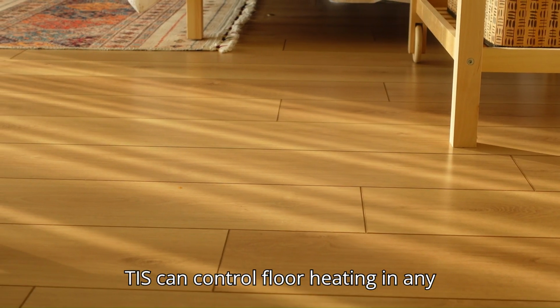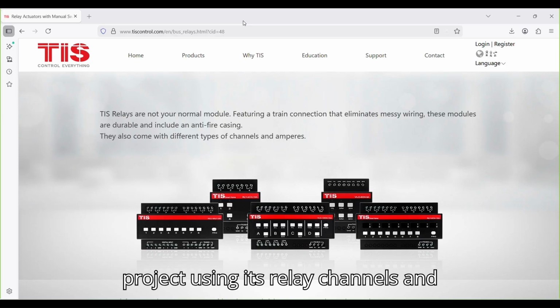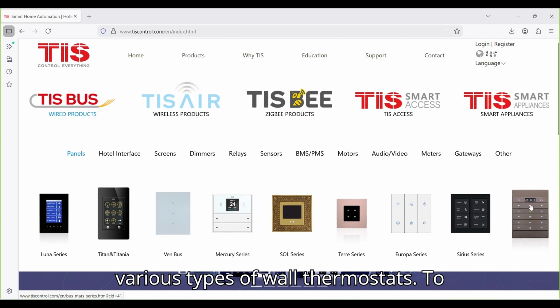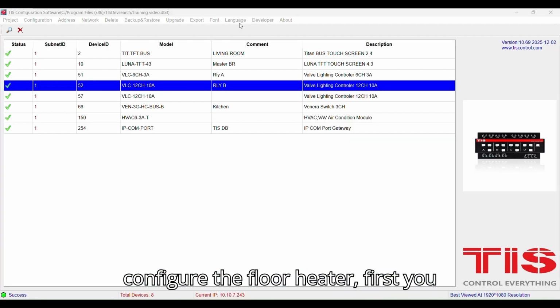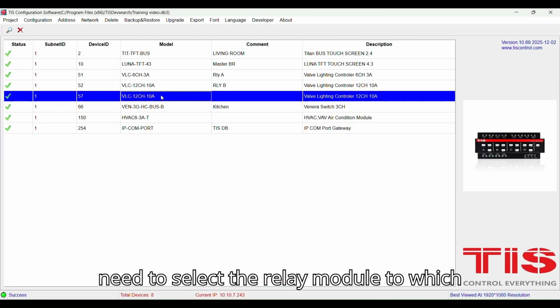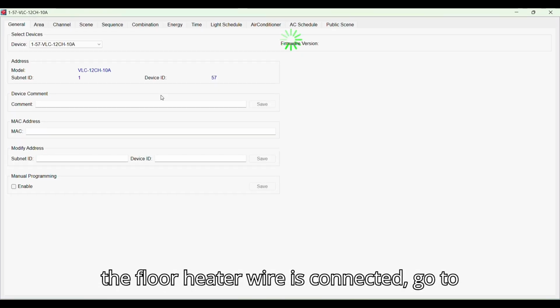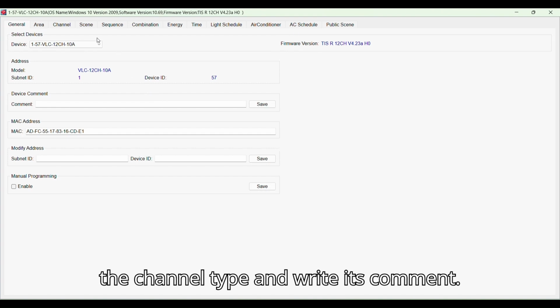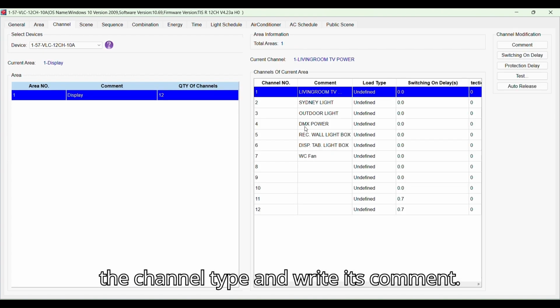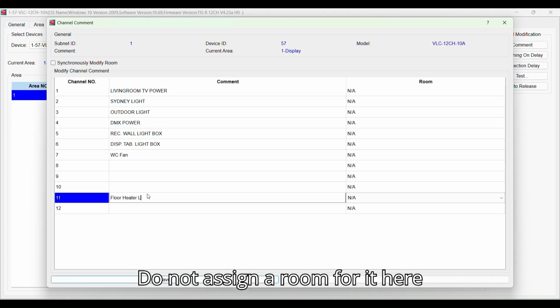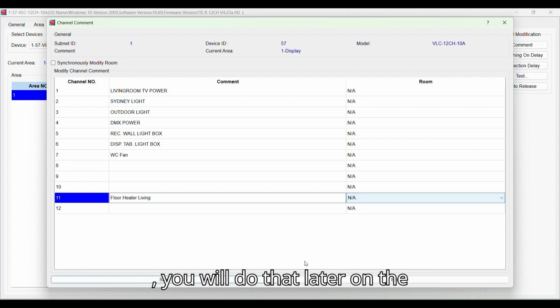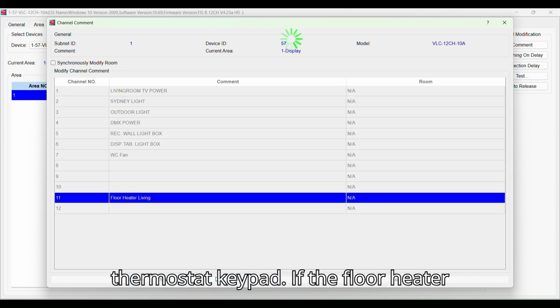TIS can control floor heating in any project using its relay channels and various types of wall thermostats. To configure the floor heater, first, you need to select the relay module to which the floor heater wire is connected. Go to the channel type and write its comment. Do not assign a room for it here. You will do that later on the thermostat keypad.